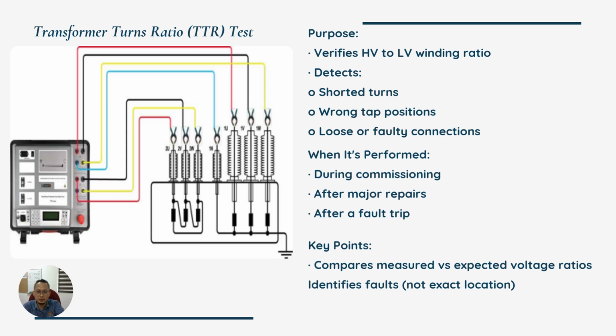Next, we have the transformer turns ratio test, which is used to verify the high voltage to low voltage winding ratio. This test helps identify shorted turns, wrong tap position, or loose or faulty connections. It is performed during commissioning, after major repairs, or following a fault trip. By comparing the measured voltage ratios with expected values, this test ensures that the transformer functions correctly before being put into service.